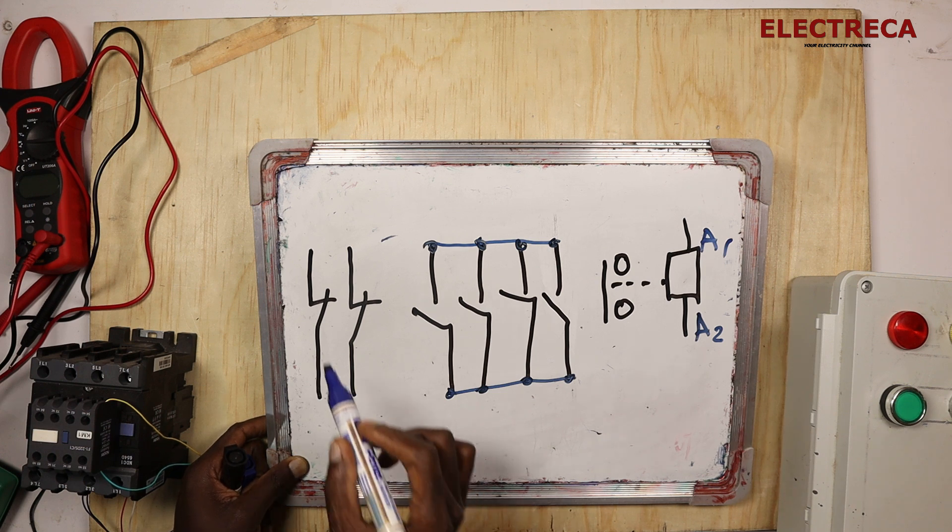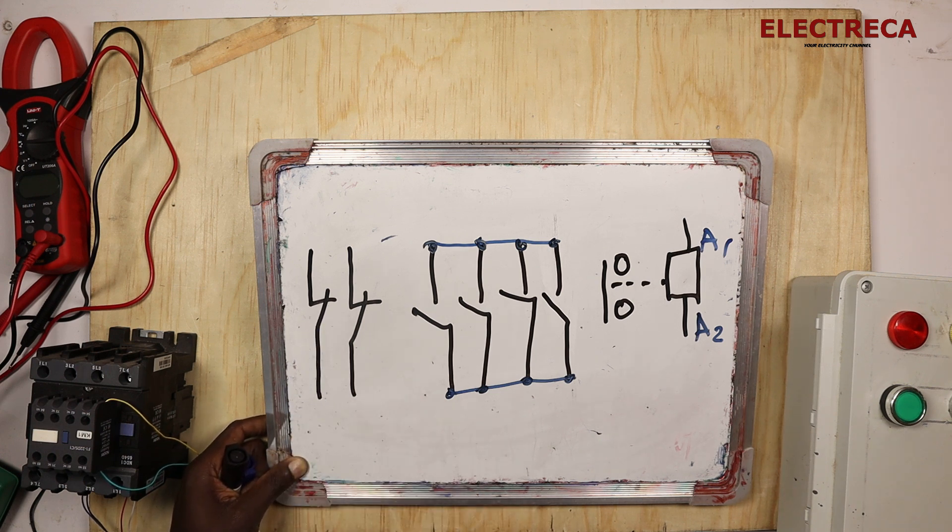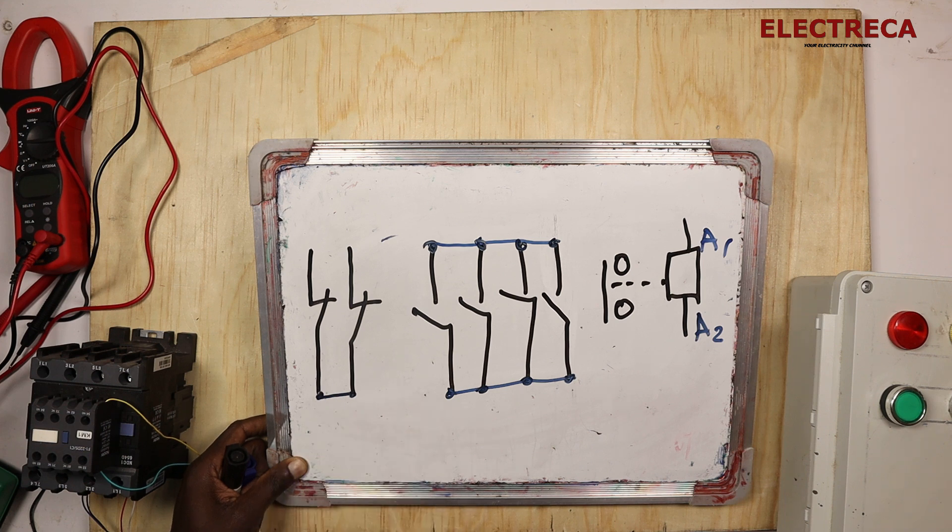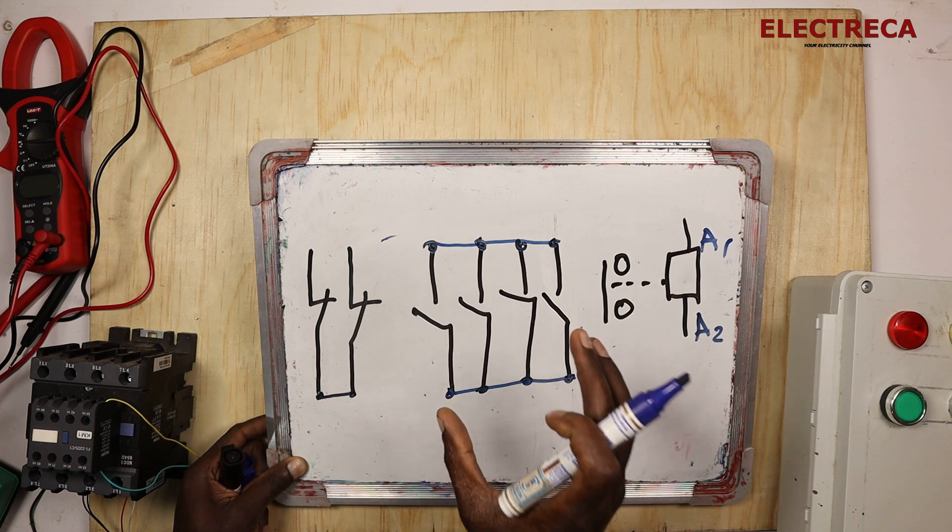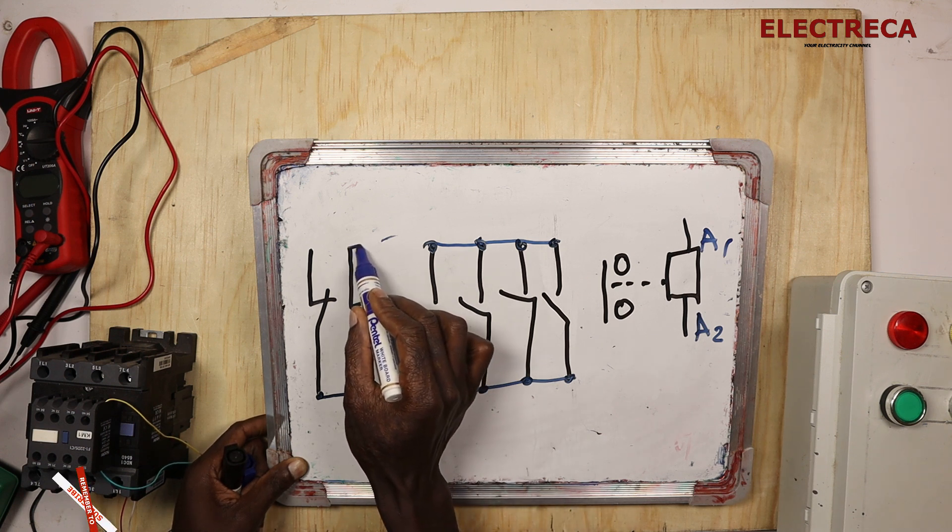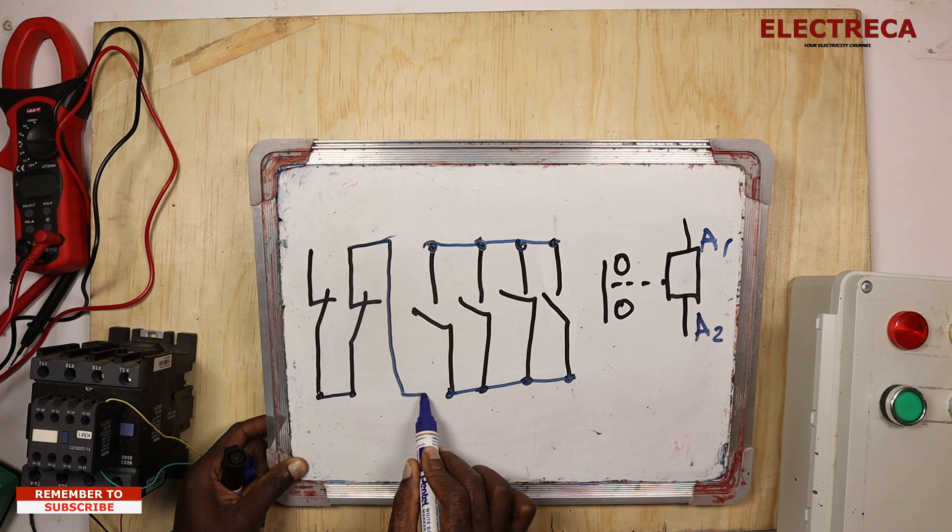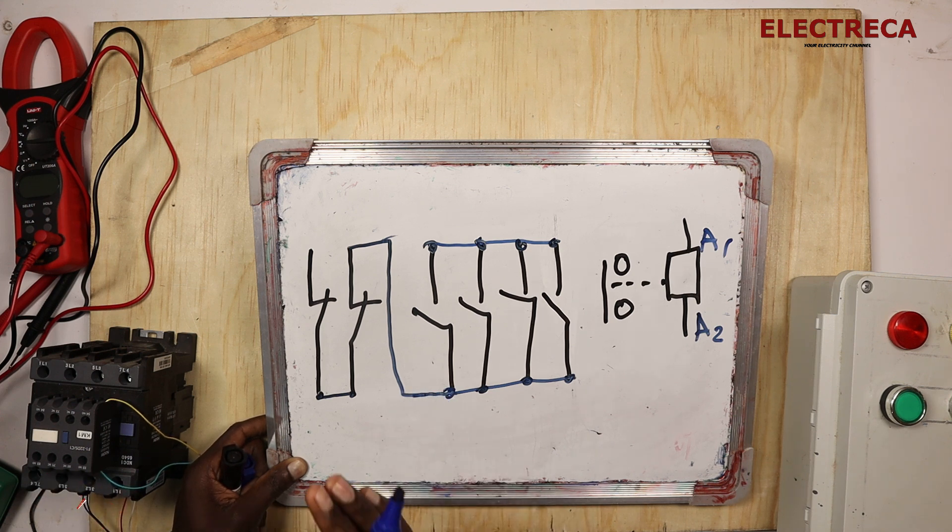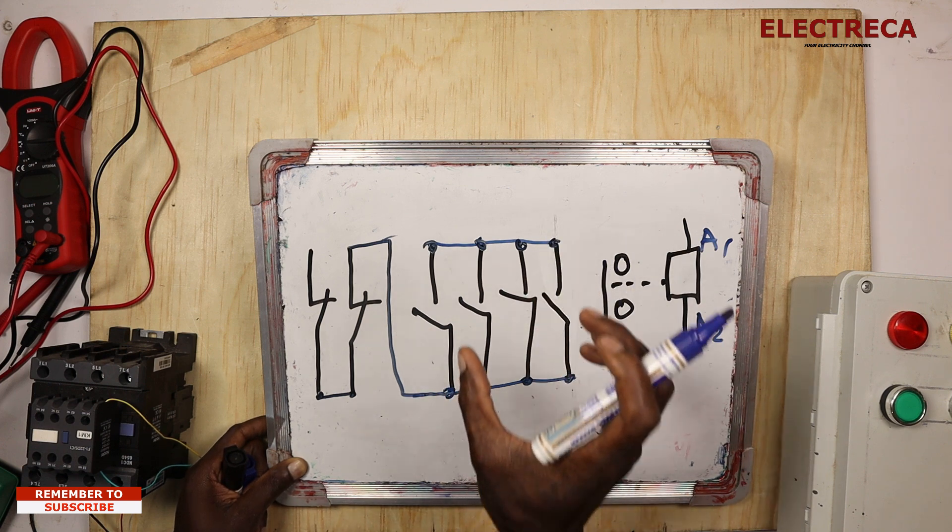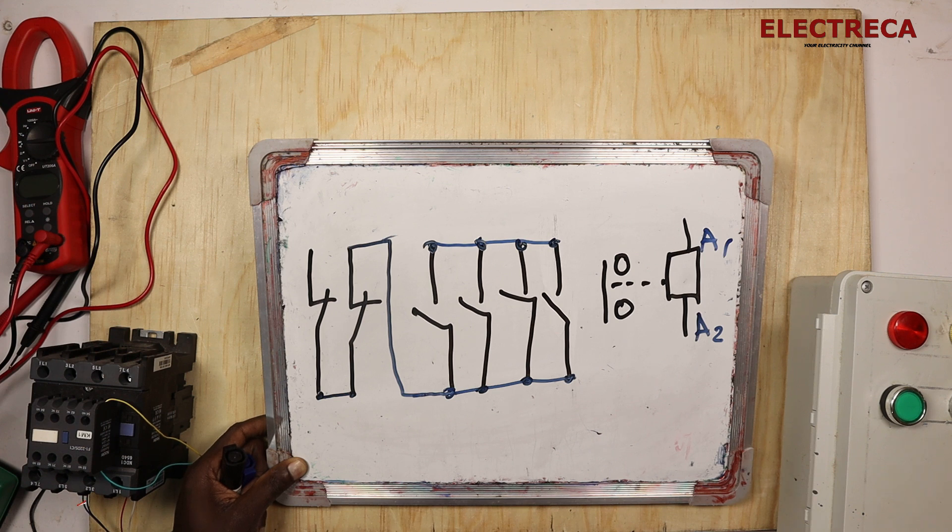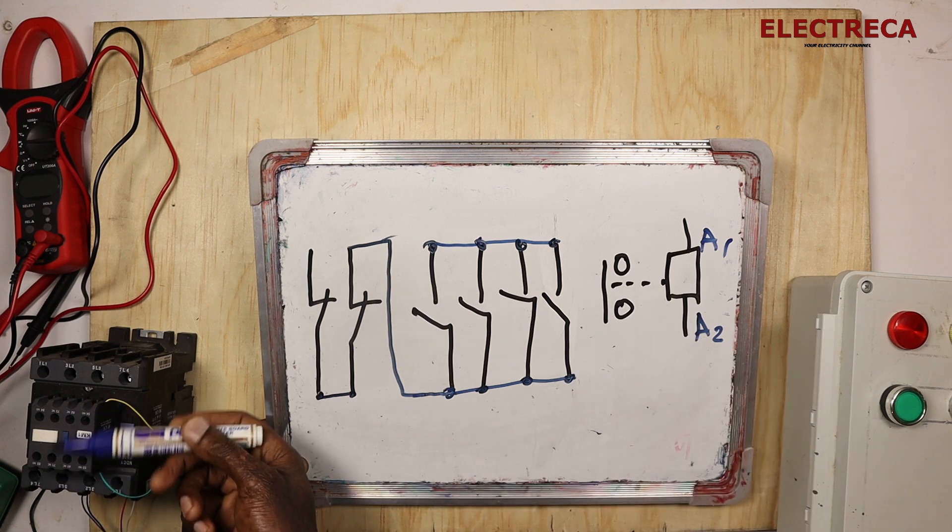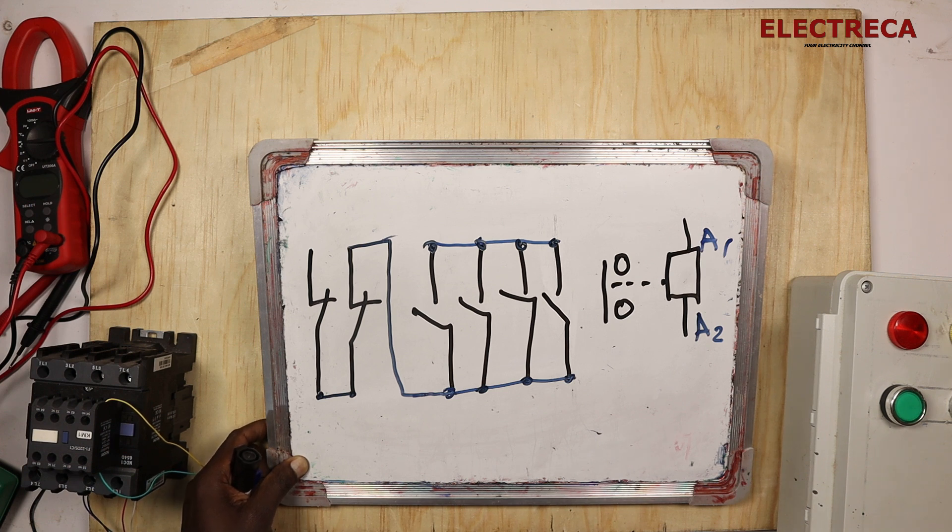Now the stop buttons we connect in series. So stop series, start parallel. Now let us connect this together. So like that, the stop button is in series with the start button. The four start buttons are connected in parallel, the two stop buttons are connected in series. Now we have our normally open here on the contactor which will help us to do the retaining or the holding position.